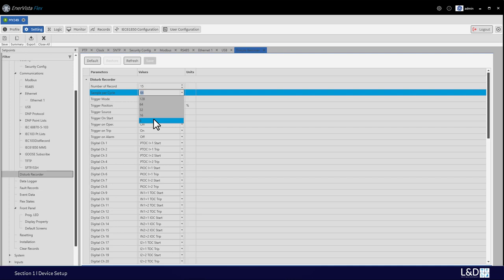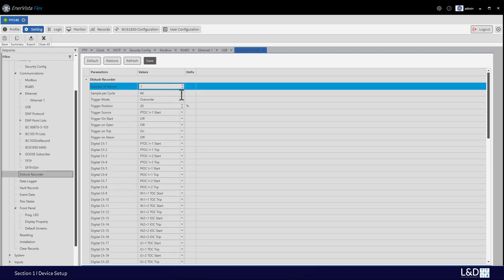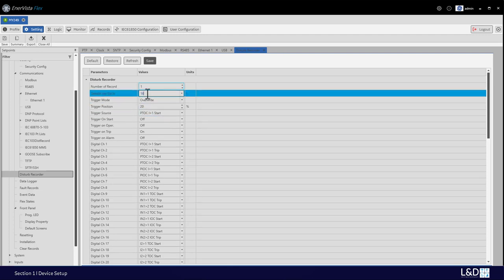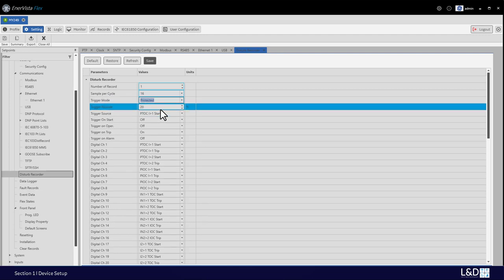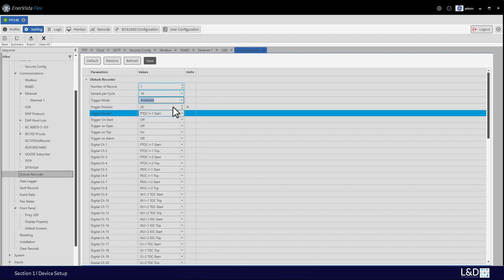The sample rate can also be set as low as 8 per cycle. If the user wants to save a longer waveform, for example a four-shot auto reclose, it's better to use a smaller number of records and a lower sample rate — this way you can save a much longer waveform. The trigger mode can be set to overwrite or protected. The default setting is overwrite, meaning new records overwrite old records so the relay always keeps the latest records. When set to protected, the relay only keeps up to the preset number of records. The trigger position lets you choose how much pre-fault and post-fault to capture.